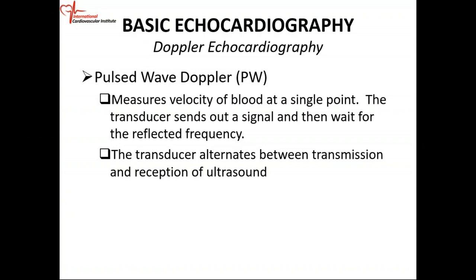Pulse wave Doppler measures low velocity. When you have your probe or transducer, it sends out an impulse, a sound wave, and then it does nothing — you wait for the reflection of that sound wave to come back. When the sound wave travels to any structure, it impinges on that structure and bounces back towards the transducer, and you get your Doppler signal. Pulse wave Doppler measures velocity of blood at a single point.